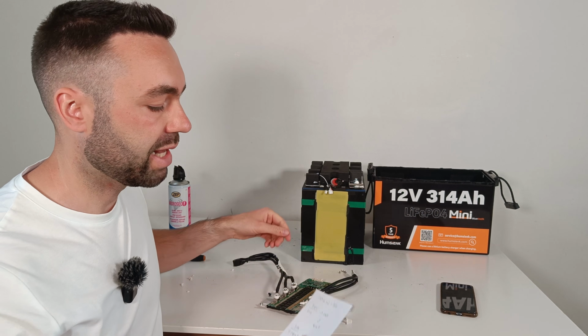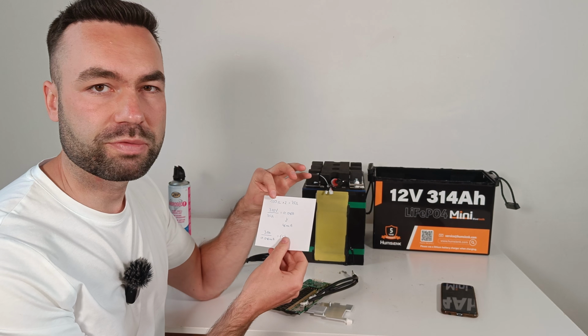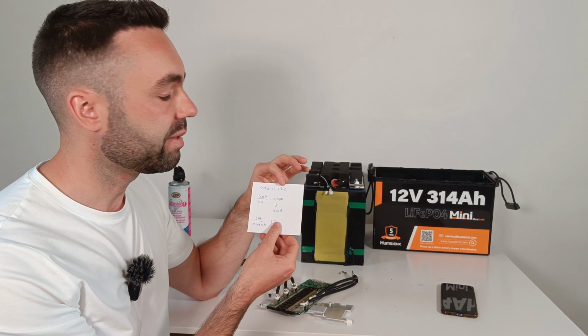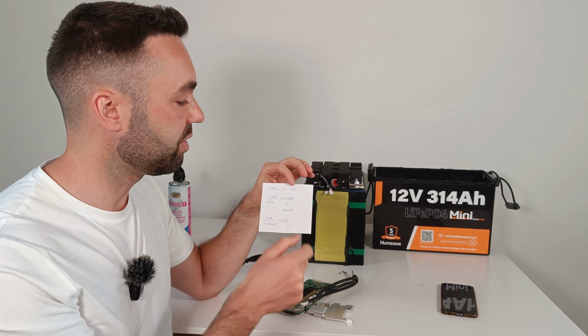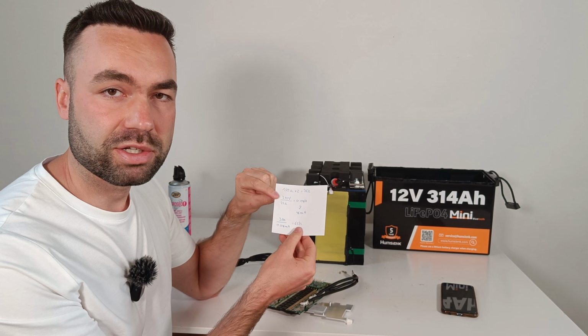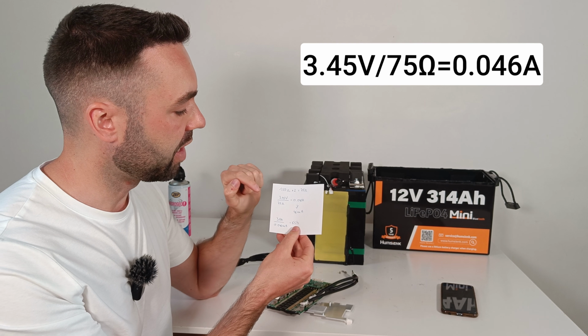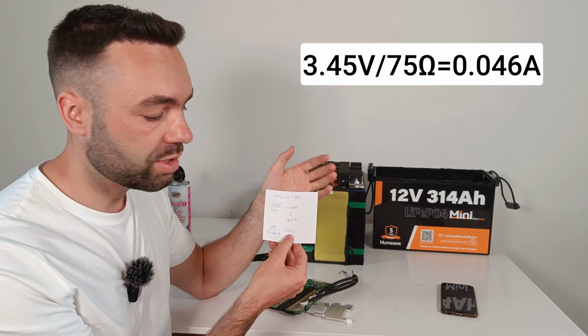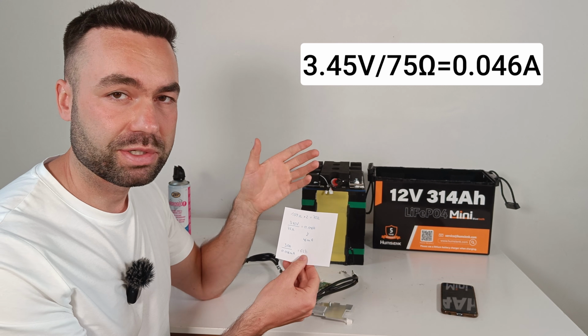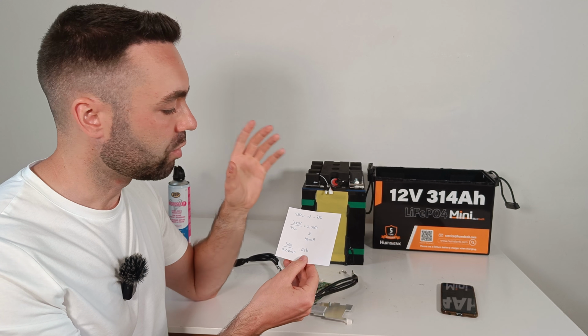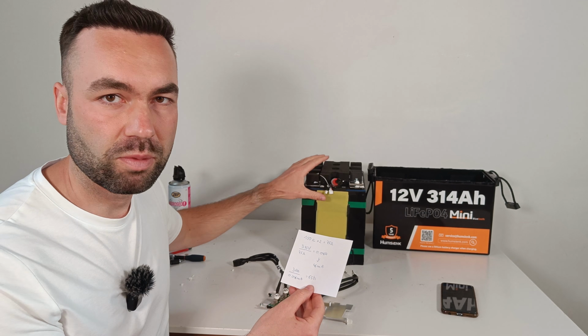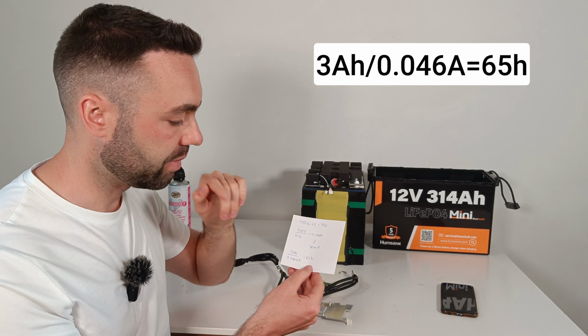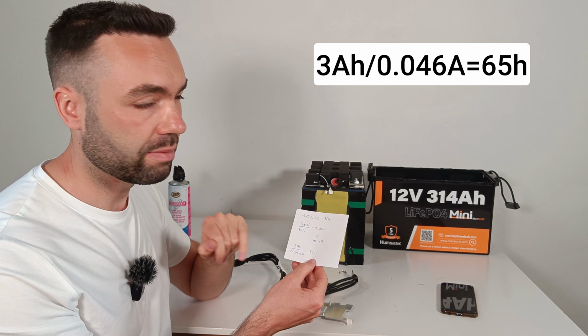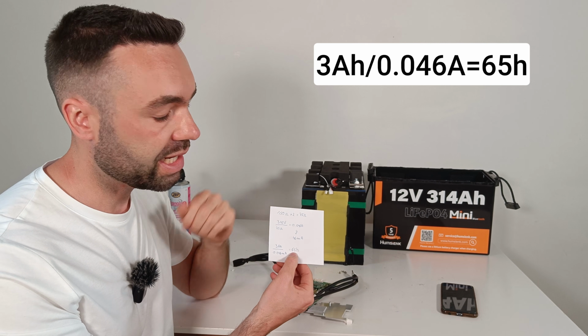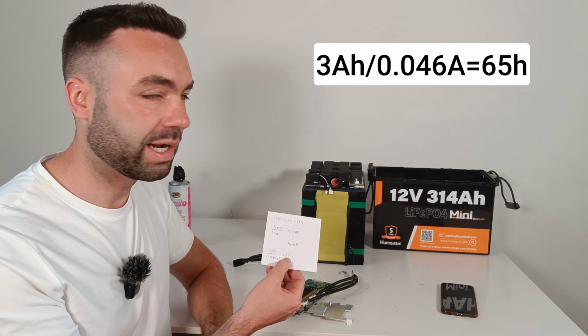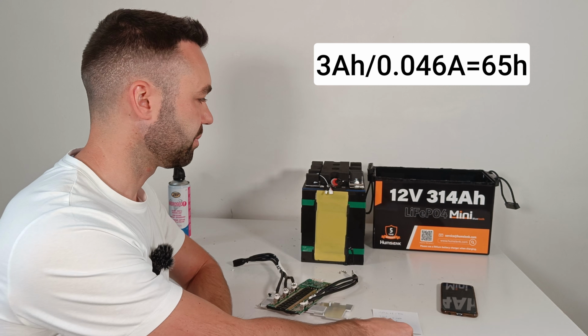If we calculate the balancing current: two 150 ohm resistors in parallel give an equivalent resistance of 75 ohms. With the balance start voltage of 3.45 volts, that gives a balance current of 45 milliamps. That's very low. Imagine the battery has an imbalance of 1%, that's 3 amp hours. Divide it by the balancing current, and it would take 65 hours to get rid of the imbalance. That's a very long time.